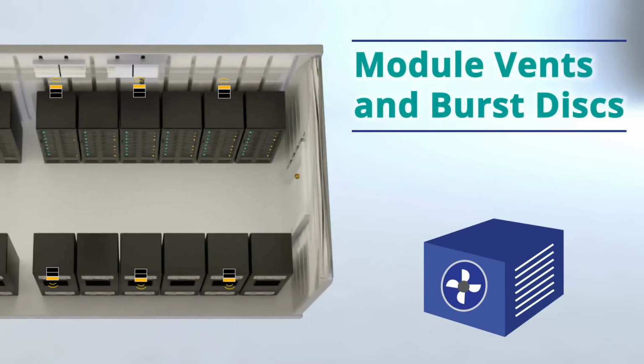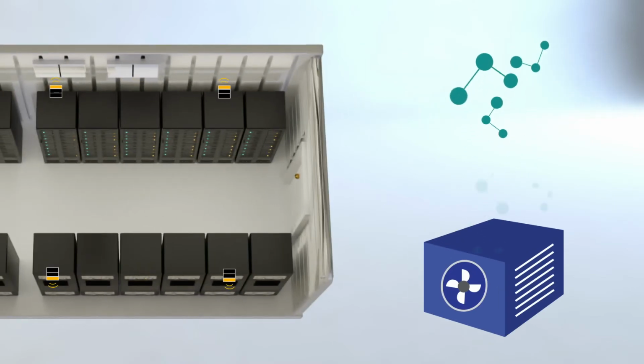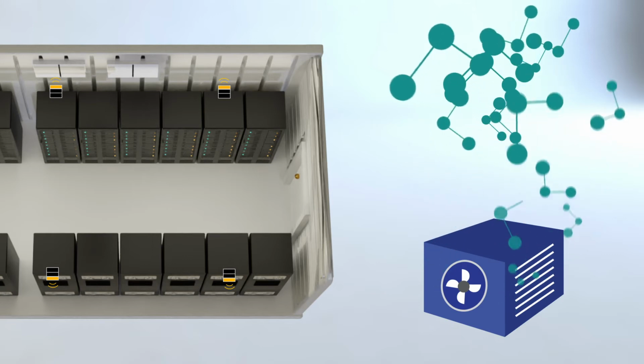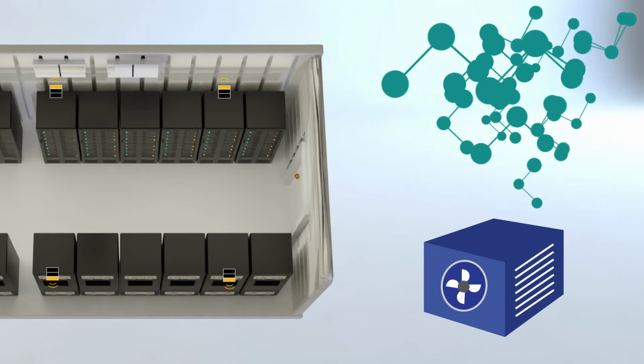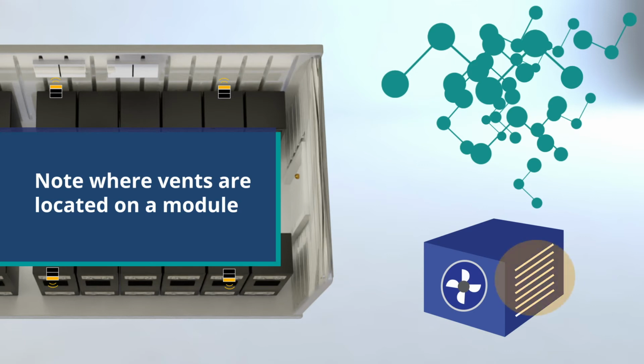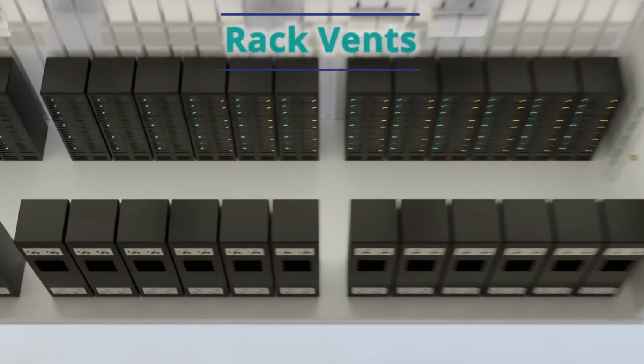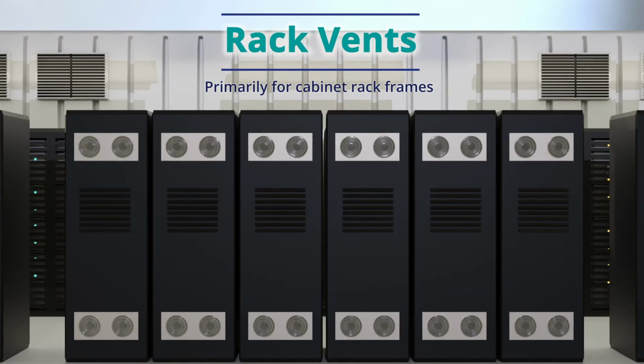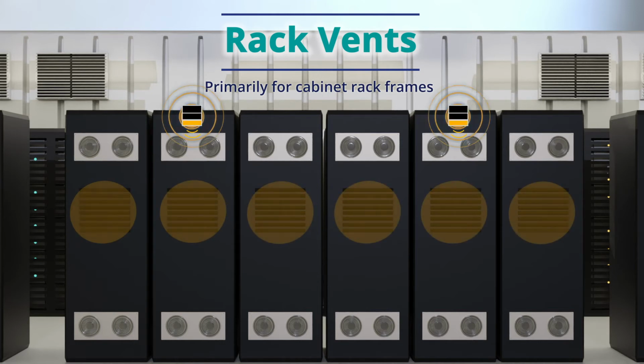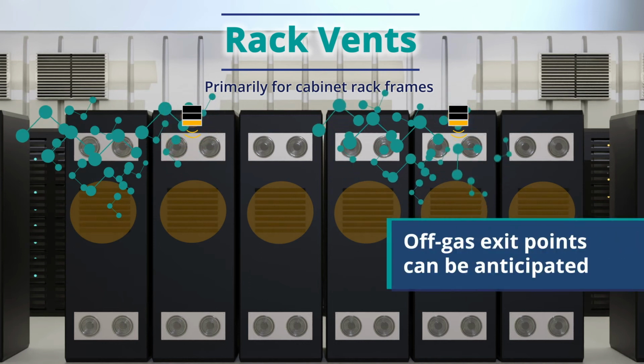Module vents and burst disc allow for sensor reductions, as the off gas will create a larger dispersion cloud due to the ease of gas escape. Always make note of where the vents are located on a module and how this can affect the flow of off gas. Rack vents, primarily for cabinet rack frames. Racks with built-in vents may allow fewer sensors. Off gas will be more guided when leaving the rack, so the exit points can be anticipated.